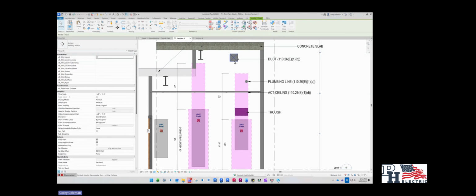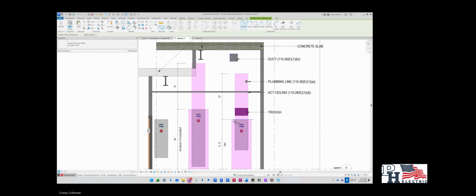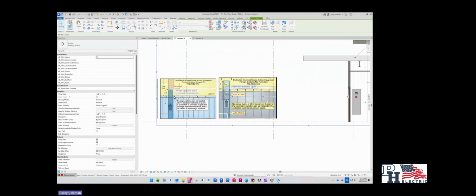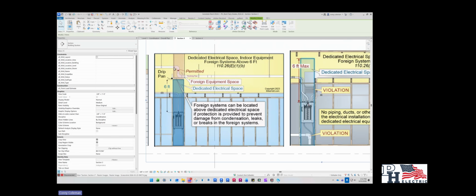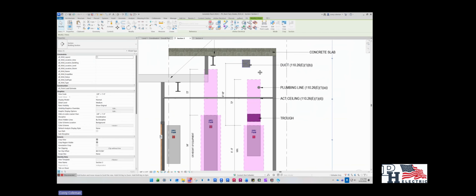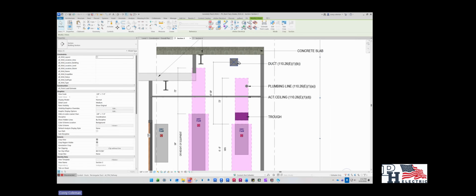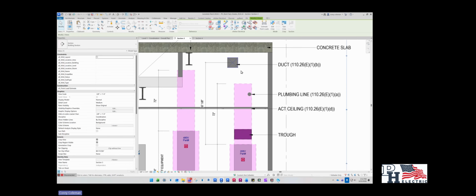Or you would have to move this duct up here. Is this a code violation based on Article 110.26? So based on the code, this foreign system is above the 6'6" space, so it is permitted to live there and that duct can stay there, but a drip pan has to be installed underneath it. In most cases, whenever we're dealing with this, we want to avoid this in all forms or fashion. The reason is that the drip pan hasn't been accounted for.